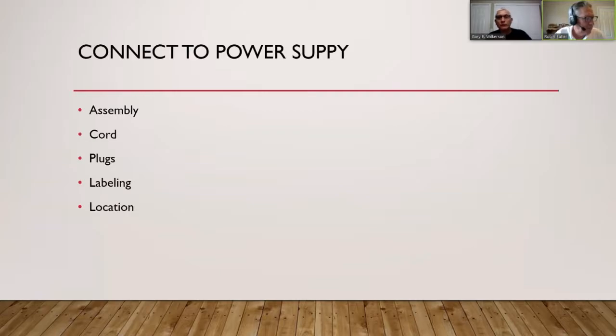With that being said, whatever the layout of your tiny home is, it may require that there is no feasible way that you can put it on the left driver's side. And if you put it somewhere else, that is okay, but it has to meet the minimum standards of the length of the cord. If you get a long cord, it's not only a tripping hazard, but more than that, it has to do with voltage drop and the heating up of the cord. So they want to keep it as short as possible, but feasibly long enough to be able to plug into sites no matter where you go in the United States or Canada, to where you can plug into their utility source and not have to add an extension cord.